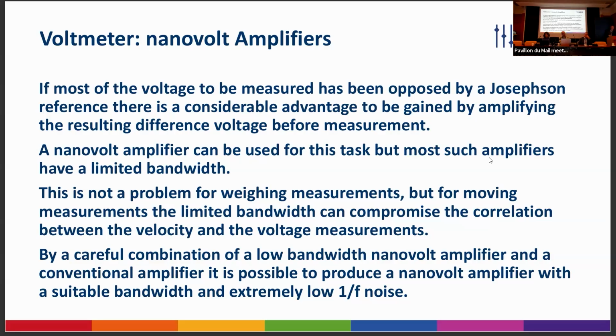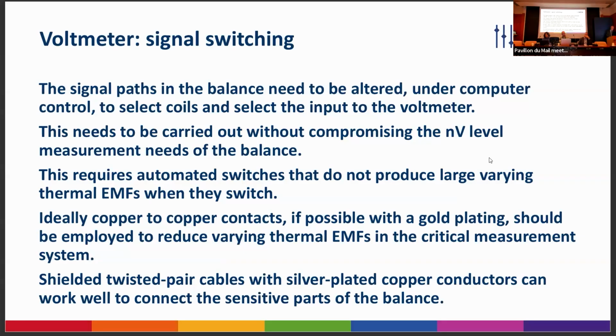It's more complicated than an ordinary nanovolt amplifier, but it gives you the ability to actually integrate properly over the moving velocity sample time and the voltage sample time.